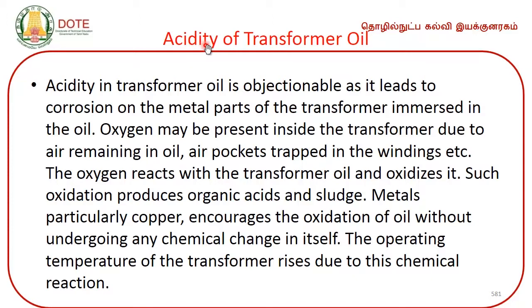Then acidity of transformer oil. Acidity in a transformer oil is objectionable as it leads to corrosion on the metal parts of the transformer immersed in the oil. Oxygen may be present inside the transformer due to air remaining in oil, air pockets trapped in the windings, etc. The oxygen reacts with the transformer oil and oxidizes it. Such oxidation produces organic acids and sludge. Metals, particularly copper, encourage the oxidation process of oil without undergoing any chemical change in itself. The operating temperature of the transformer rises due to this chemical reaction.